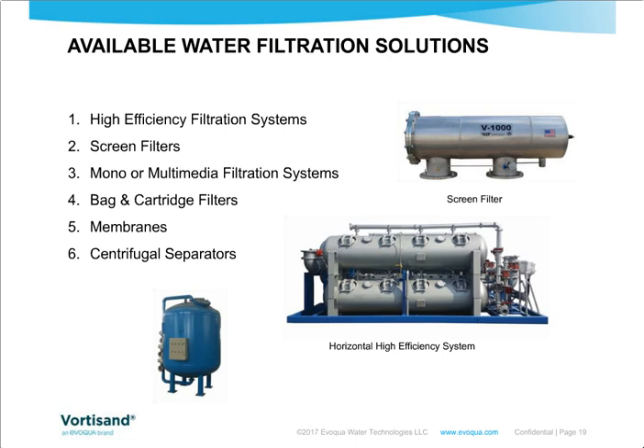And then centrifugal separators. Another great technology if you're focusing on larger particles. This technology requires a significant amount of flow or pumping requirements, high horsepower pumps that use high flow to create a centrifugal force to separate out particles based upon density. So you need to understand the differences between the different technologies to properly select a filter, not only for your application from a water quality perspective, but also for what your facility dictates. Now let's look at the difference between some of these technologies.